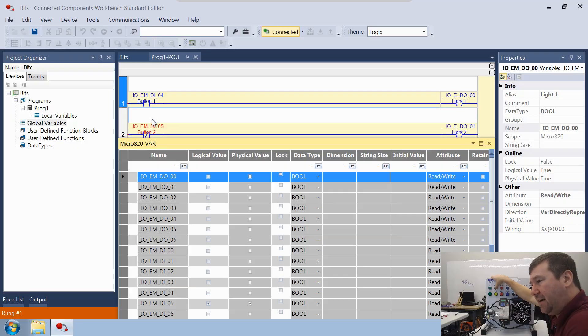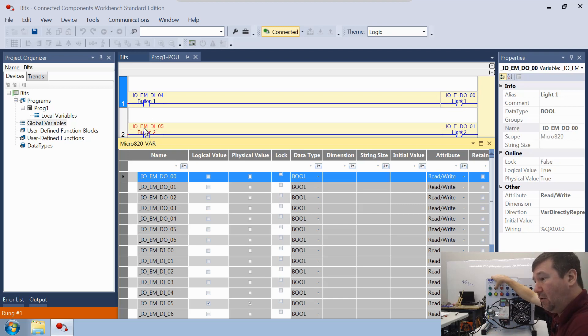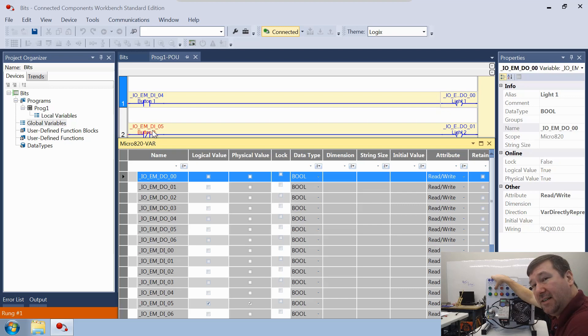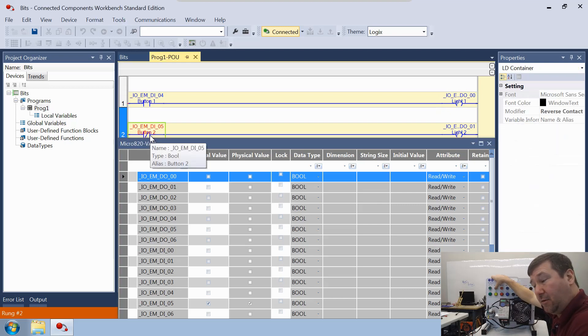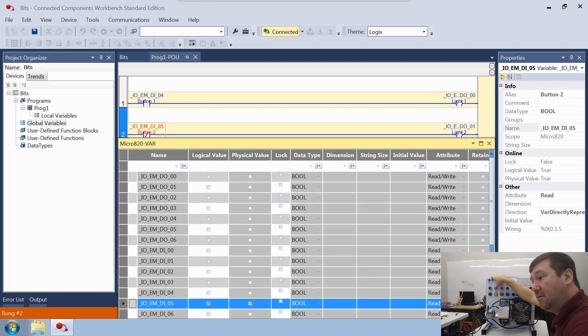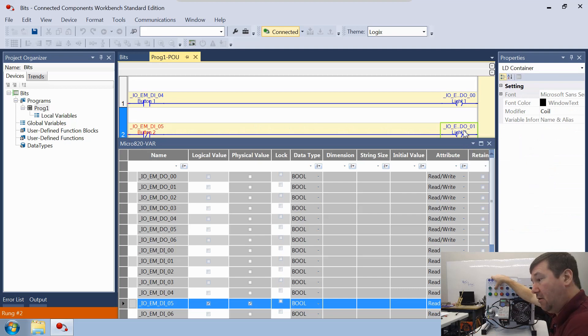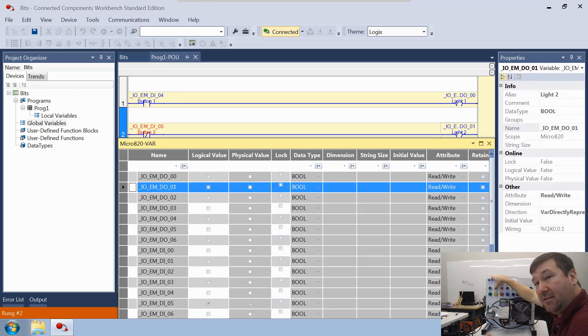So now let's press Button 2. We see it looks a little funny — we have a little bit of red here and a little bit of blue here. The red is the condition of the input, meaning if Input 5 is red, the box has a 1 in it. But this Reverse Contact says go look for a 0 at Input 5 — do I have one? No, the box is checked, so it's a 1. So this instruction is false, shown by the blue. It passes false conditions to our coil, a false coil goes and writes a 0 to Output 1, and that is why the light is out.